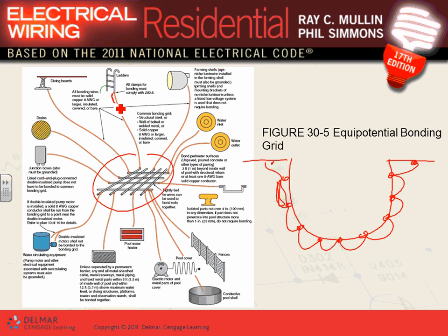Can you guys see that with this conductor, number 8 copper? Everything around the swimming pool, from the drain to the diving board, the ladder, and the fences, will be bonded with number 8 to the grid made by the rebars of the concrete swimming pool. The frame of the motors, can you see the frame of that motor is also bonded to it. Heaters are bonded, all of them with number 8. By doing it this way, guys, you minimize the possibility of people standing in one location at 0 voltage and touching another location that's at higher voltage.